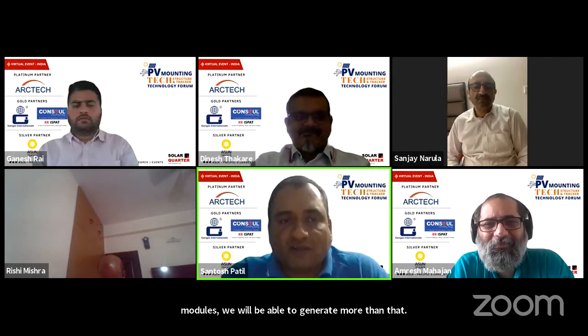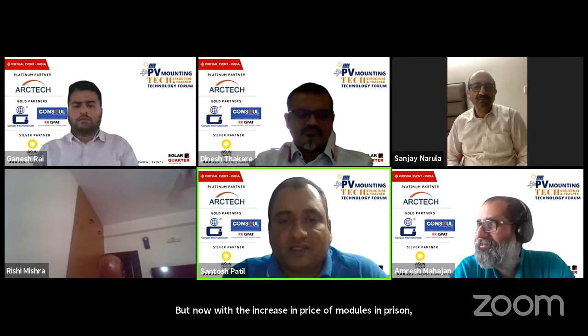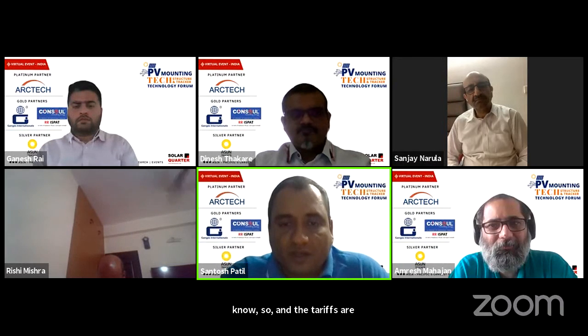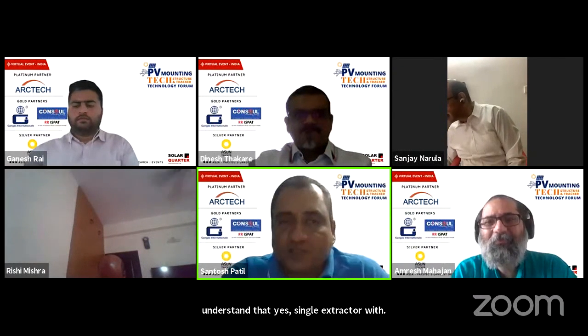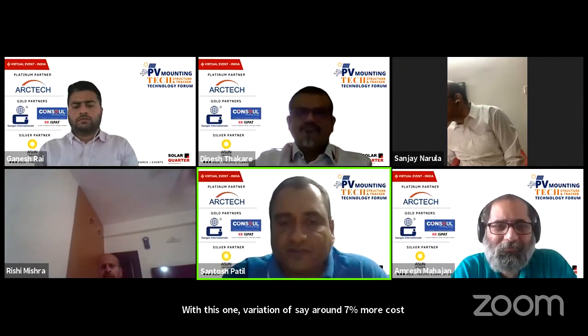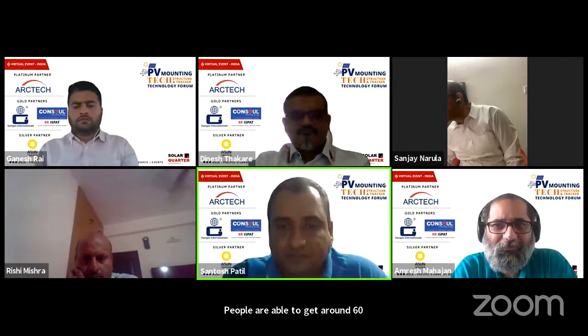But now with the increase in price of modules, increase in the cost of other materials, like steel is at its highest now, and the tariffs are the same. So now people have to understand that yes, single axis tracker with bifacial module, or the module with higher watt-peak capacity, has to be used. We have done a calculation also: with a small variation of around 7% more cost when compared to the fixed tilt, people are able to get around 6 to 7% more generation.